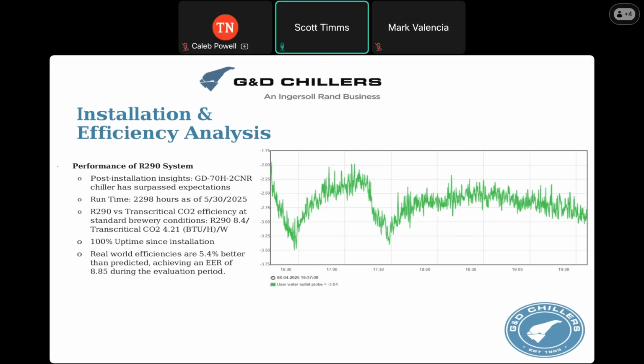Installation efficiency analysis. Whenever we did this slide the first time, it was back in May of last year, so we have a full additional year of running, and this has just remained true the entire time. We've had zero downtime in that time, knocking on wood, and still have had zero downtime in the full year that we've had it running as well. We were able to see that at these brewery conditions, we did get this 8.4 EER, and we actually got a little bit better than that in our real world efficiencies - we were able to get 8.85 as compared to the 8.4 expected in the sizing software. So we were able to actually see what was expected, which is always nice.